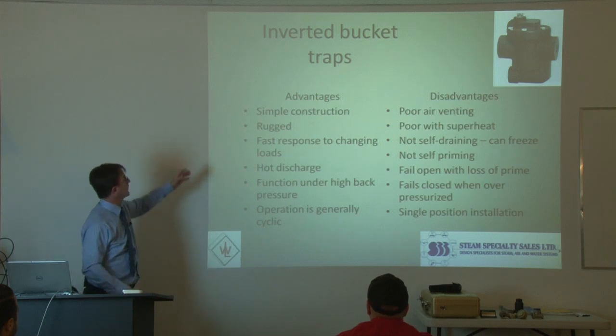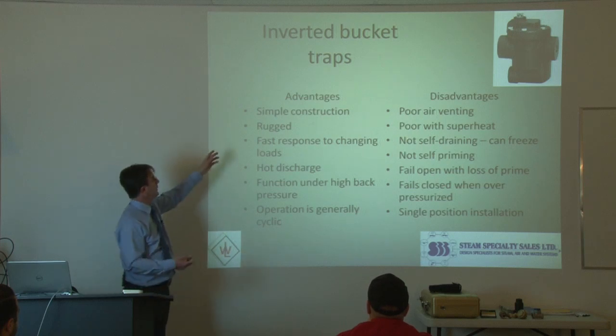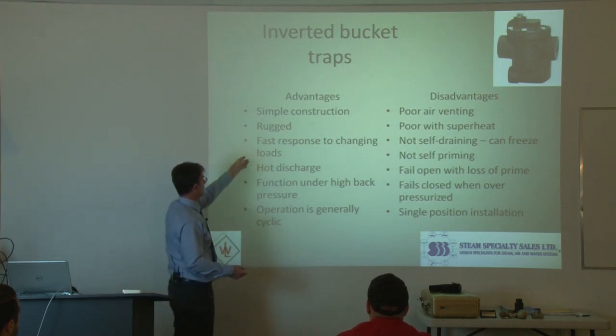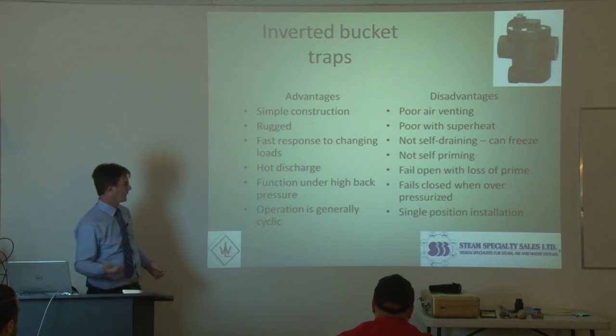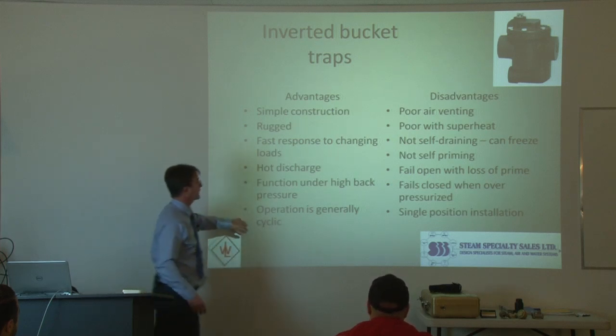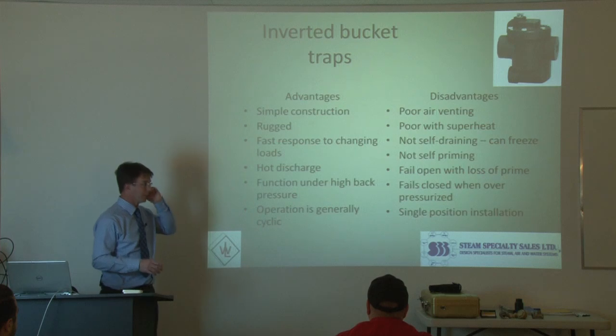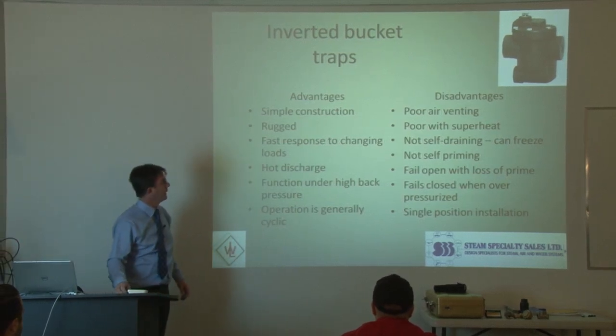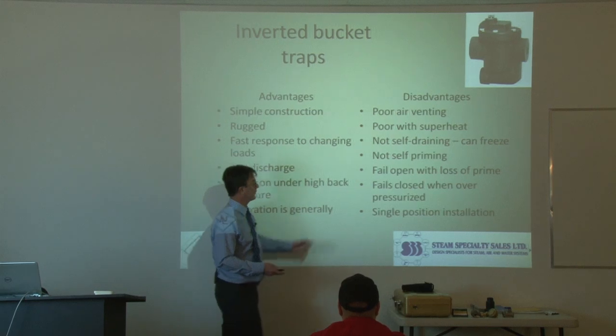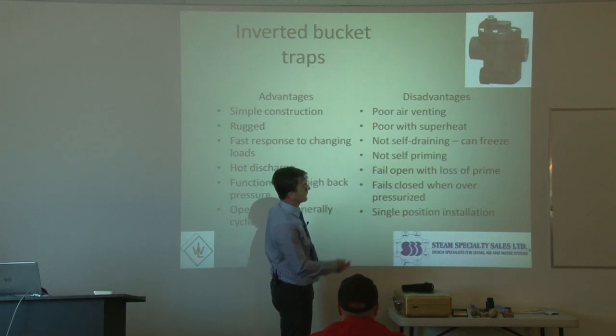Advantages of the inverted bucket trap include ruggedness — they're often used in demanding environments like factories, laundries, and dry cleaning operations because they can withstand a lot of abuse. They're fast responding to changes in load, discharge condensate at steam temperature (hot discharge), and operate in cyclical on-off fashion. Disadvantages include poor air venting since they have no separate air vent, poor performance with superheat, and they can freeze in outdoor applications if steam is shut off, since they're designed to hold some water inside the bucket, which can crack the body.